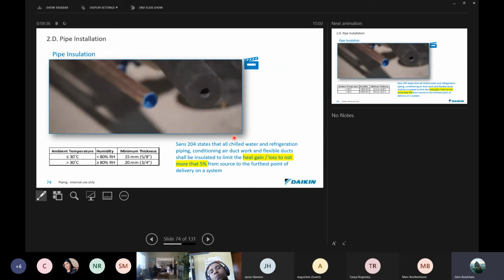We were quite shocked. We did some work over in Mauritius, and we saw that their spec there was 1 inch. And it really looked very different. In fact, at first glance at the piping, we thought we were looking at chill water piping, and then realized, no, that was actually the VRV piping, because we just weren't used to seeing such thick Armaflex on pipes. So just consider that. The guys will always tell us, oh, but we can't get the size Armaflex. The reason why you can't get it is because the suppliers have never had to order it. But it is a specification made in the SANS guide, and we should be looking at using thicker Armaflex.